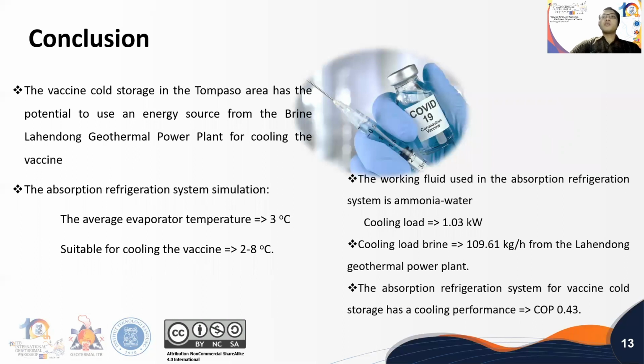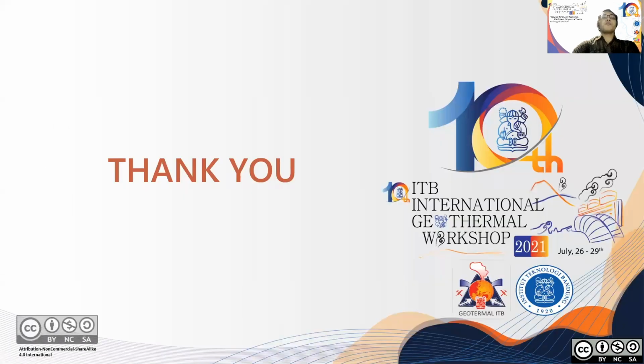The working fluid used in the absorption refrigeration system is ammonia water, with a cooling load of 1.03 kilowatt, and the cooling load brine is equal to 109.61 kilogram per hour from the Lahendong geothermal power plant. The absorption refrigeration system for vaccine cold storage has a cooling performance, or COP, equal to 0.43.